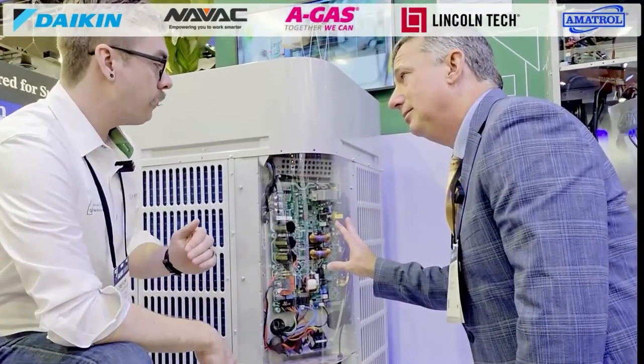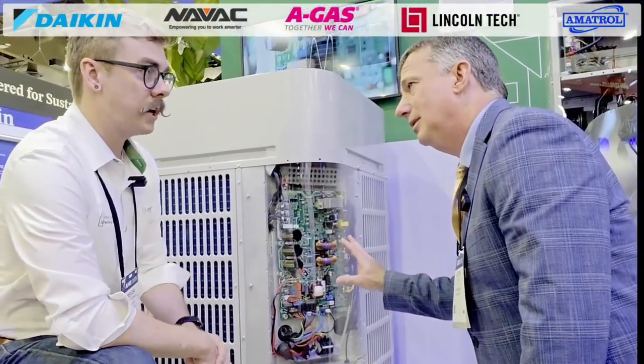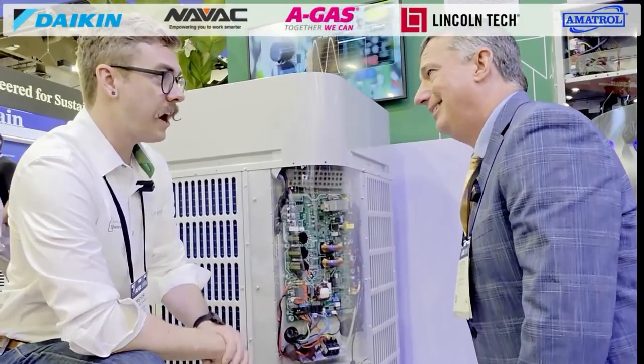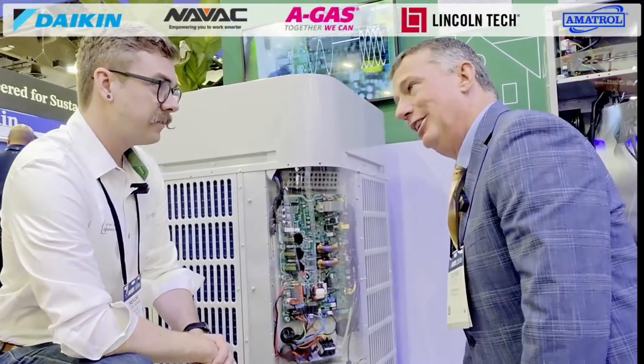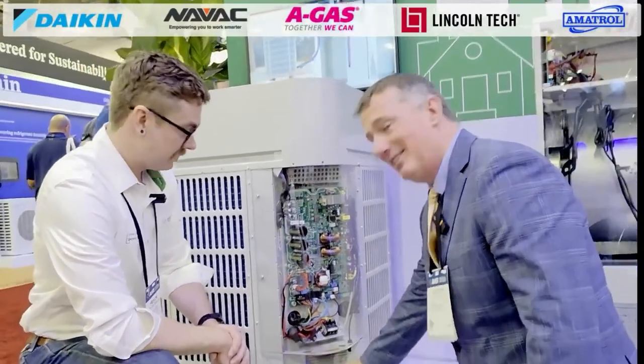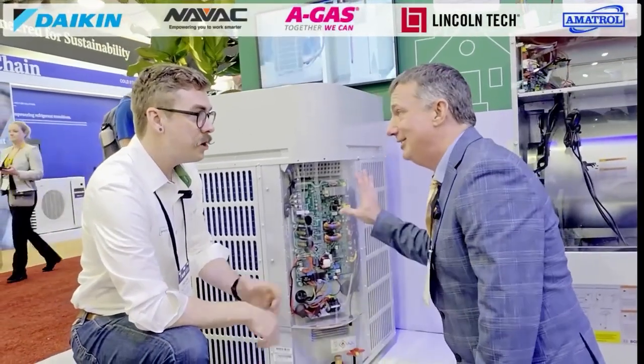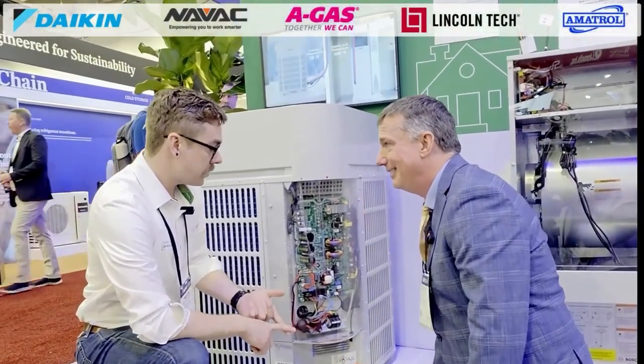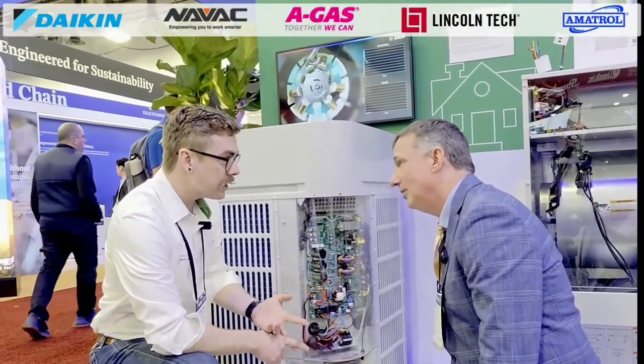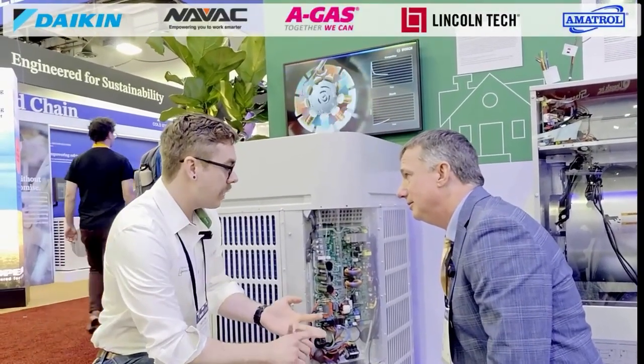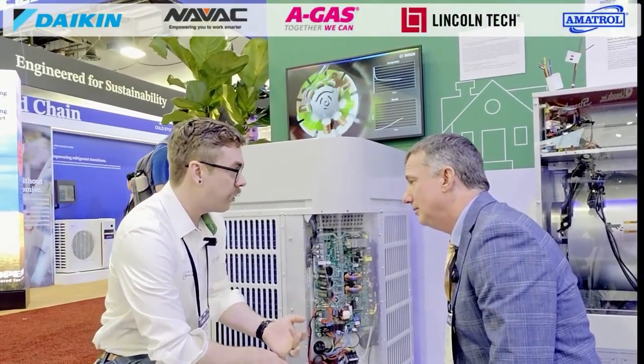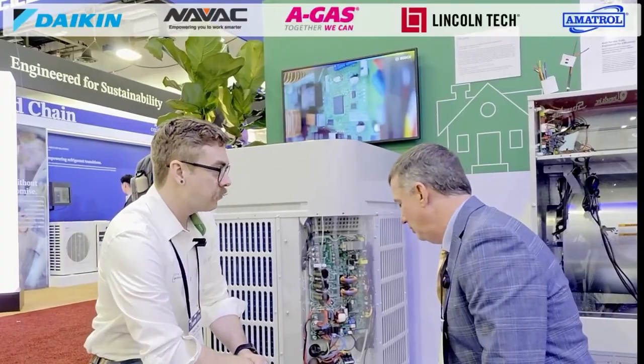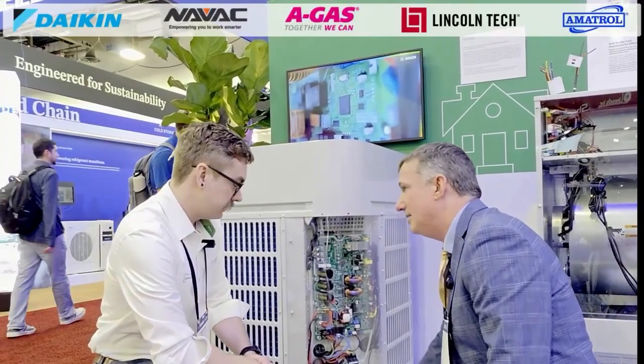Is this just this unit? No, over time we're going to phase this into the rest of our lineup. Look forward to seeing mechanical press fittings on all of the Daikin unitary products. Huge time savings - no more brazing with nitrogen, saves you from getting fire permits, fire watches, things like that. Huge reduction in risk and liability. Haven't seen that from anybody yet.